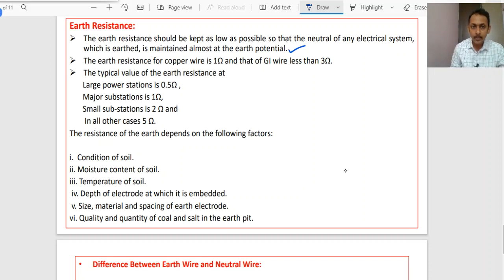For example, the typical value of earth resistance at power stations will be around 0.5 ohms. For major substations it will be 1 ohm, for small substations it is 2 ohms, and for all other cases it can be 5 ohms. Now depending upon the wire, for example, the earth resistance of copper wire will be 1 ohm, and for galvanized iron wire it will be less than 3 ohms.